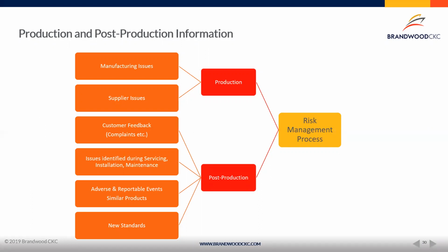and determine whether or not the risks that are newly identified, because you may not have seen those up front, or even just changes to your original assumptions of the use of the device and its probability and severity, you need to put those back into the risk management process and then determine whether or not they're acceptable and appropriately apply any controls.